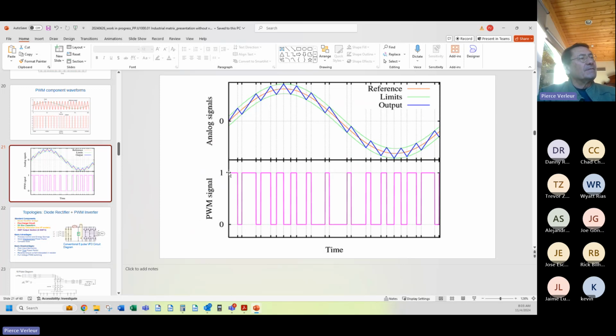Pulse width modulation means I can vary the pulse width. Notice that this one's wider than this one. They get narrower and narrower. They start to grow again. Depending on where we are in the sine wave that we are trying to simulate, red being the perfect reference or target, we're using voltage pulse width modulation to create an analog current sine wave to the motor. We want red. What we actually get is blue, because every time we pulse on, the current obviously goes up in the motor. When we pulse off, the current starts to drop, coincident with this gap, this off time. And then we pulse on again, and we climb further up the sine wave.